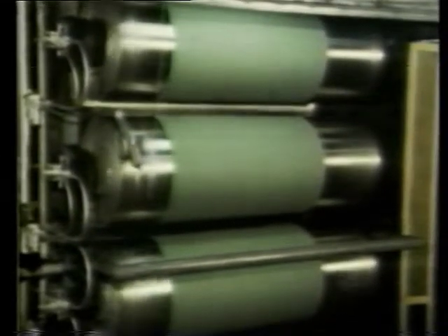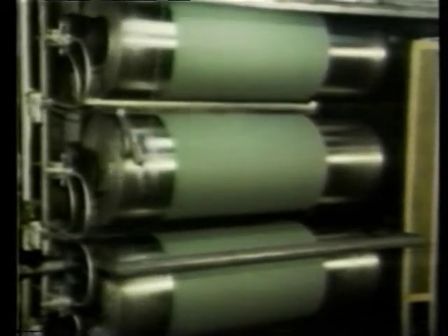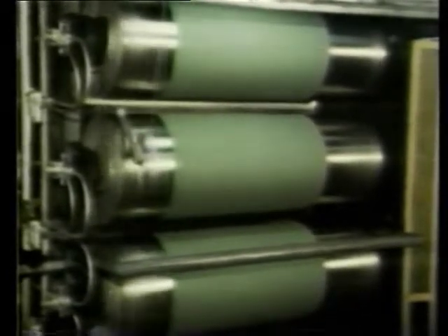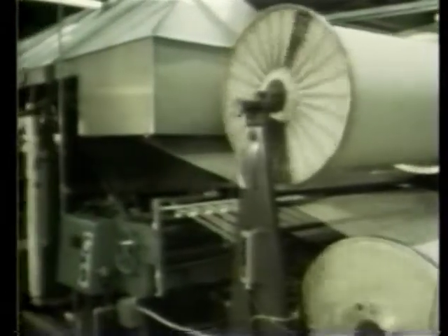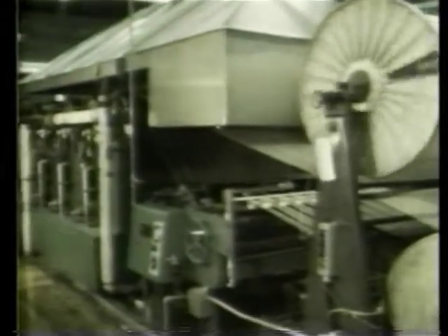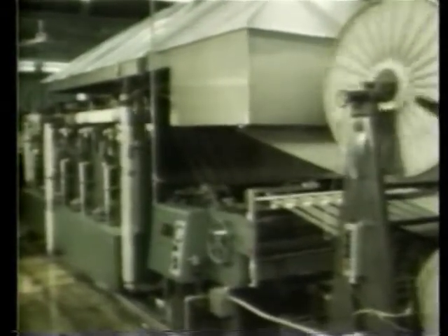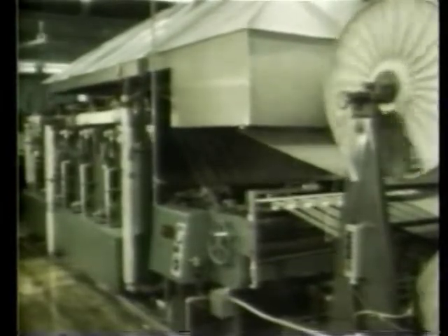Rotary cylinders. Foremost among the heat transfer equipment used in the textile industry are rotating steam-heated cylinders, such as dry cans, slashers, draw frame rolls, and sanforizers. Dry cans are typically used to dry cloth or heat set a non-woven web after the moisture has been evaporated. The rotary cylinders of the slasher dry a starch coating called size, which is applied to yarn in preparation for weaving. Synthetic fibers are heated and stretched on draw frame rolls. The sanforizer pre-shrinks fabric by wetting the material and then running it over one or two dryer cylinders.